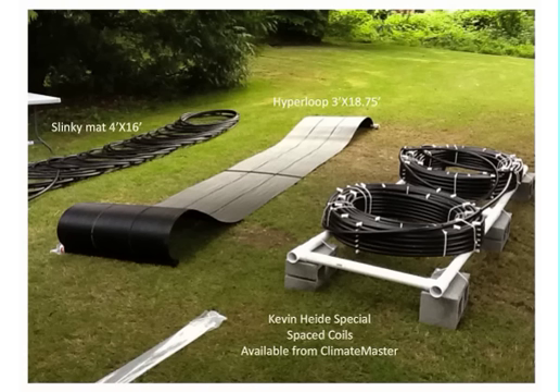I would then put some steel pipe, typically 1 inch or 1.25 inch, galvanized if I could find enough, inside those 2-inch PVC tubes and put another cap on the outside. What did I just do? I added weight - it's not rubbing against my coils, and it's evenly distributed in length and width. I also used a slinky template to create my slinky mats so they were uniformly the same dimension, typically about 16 feet by 4 feet.